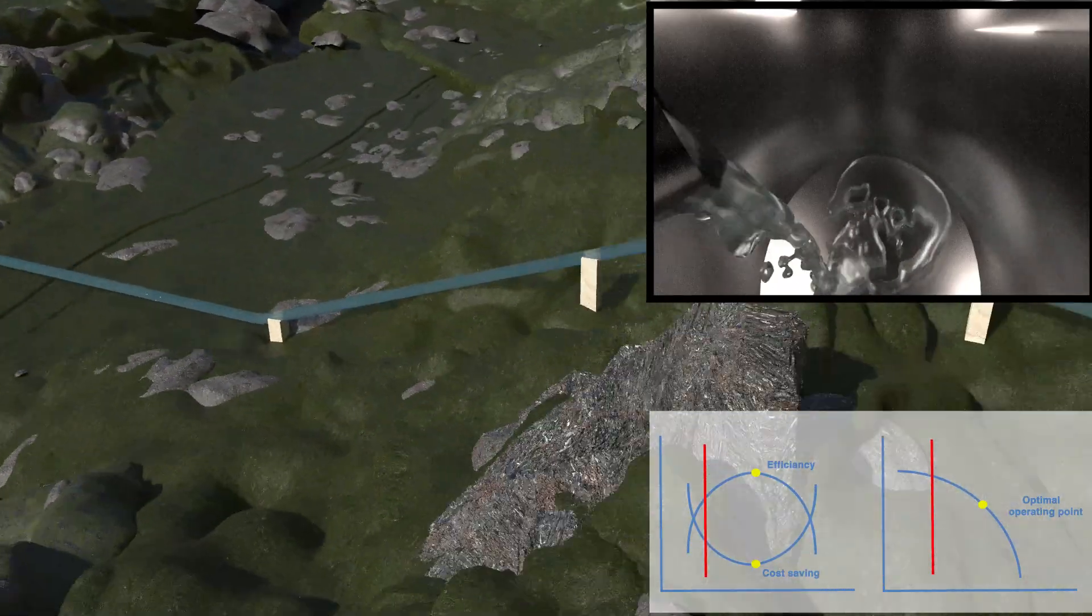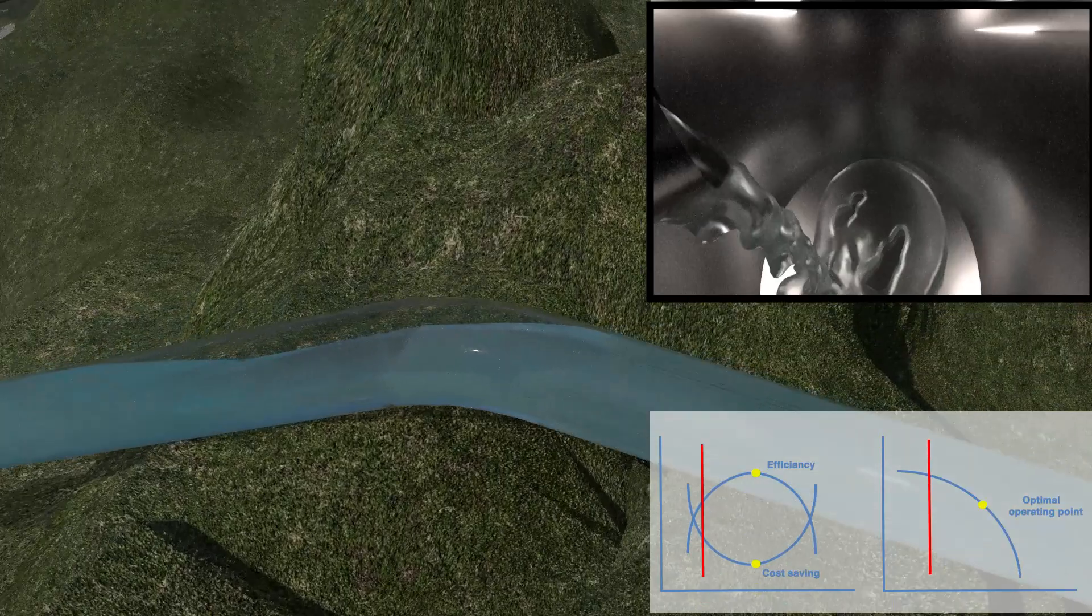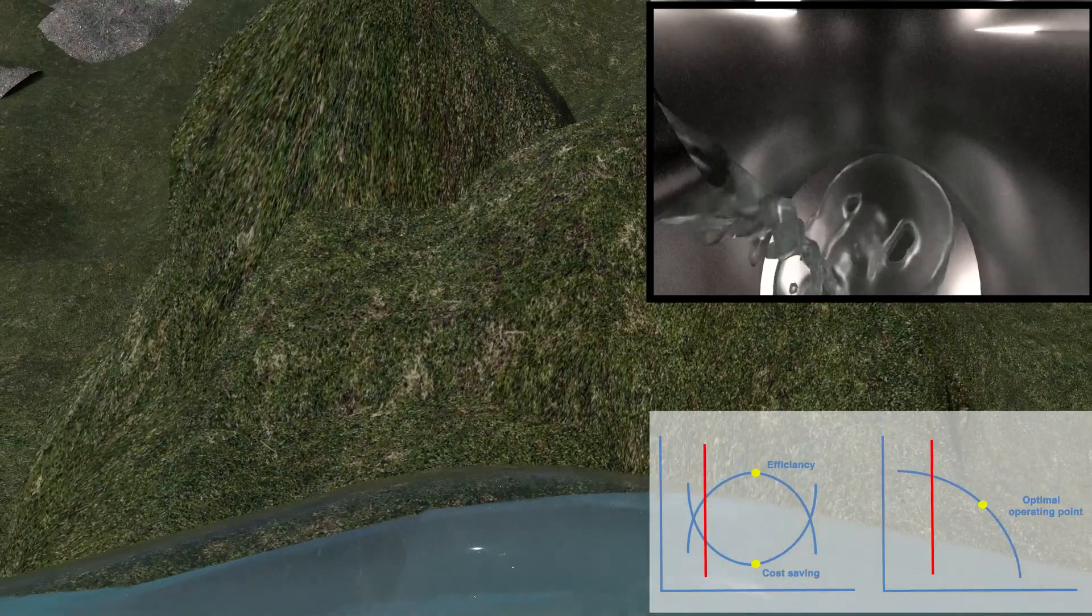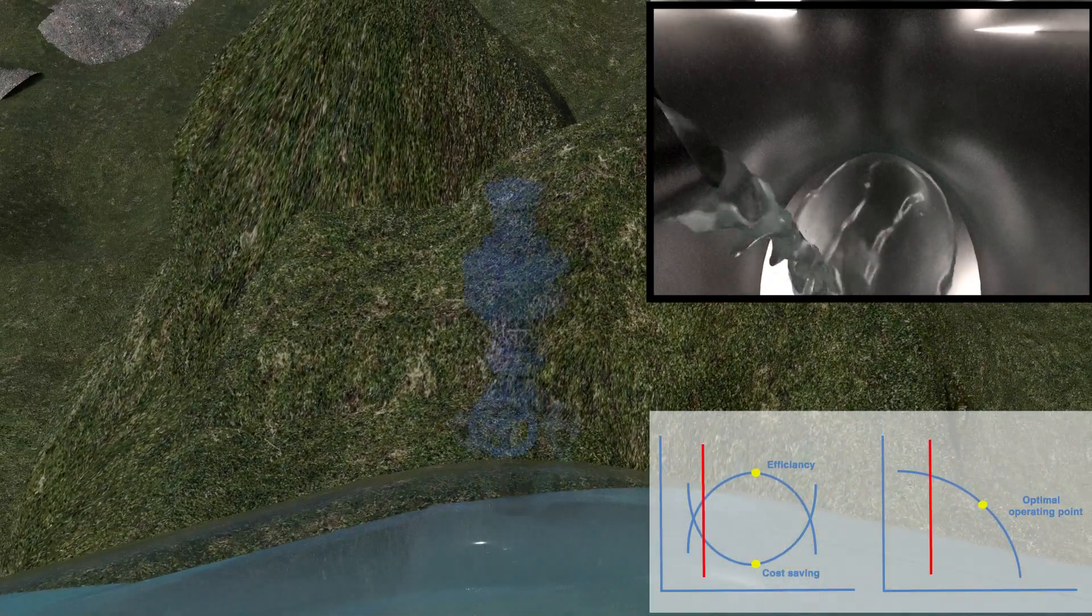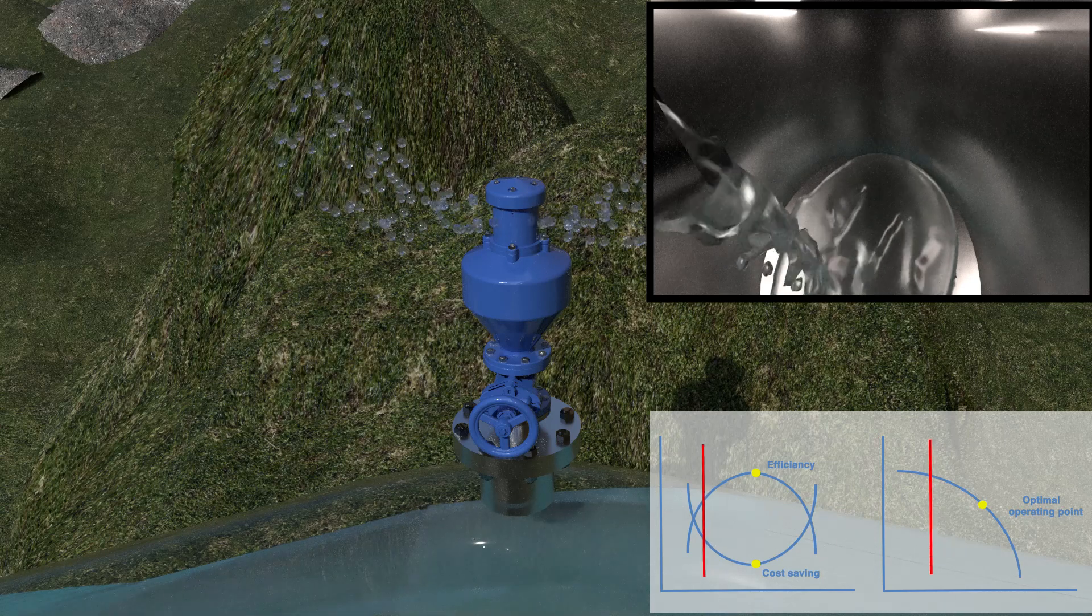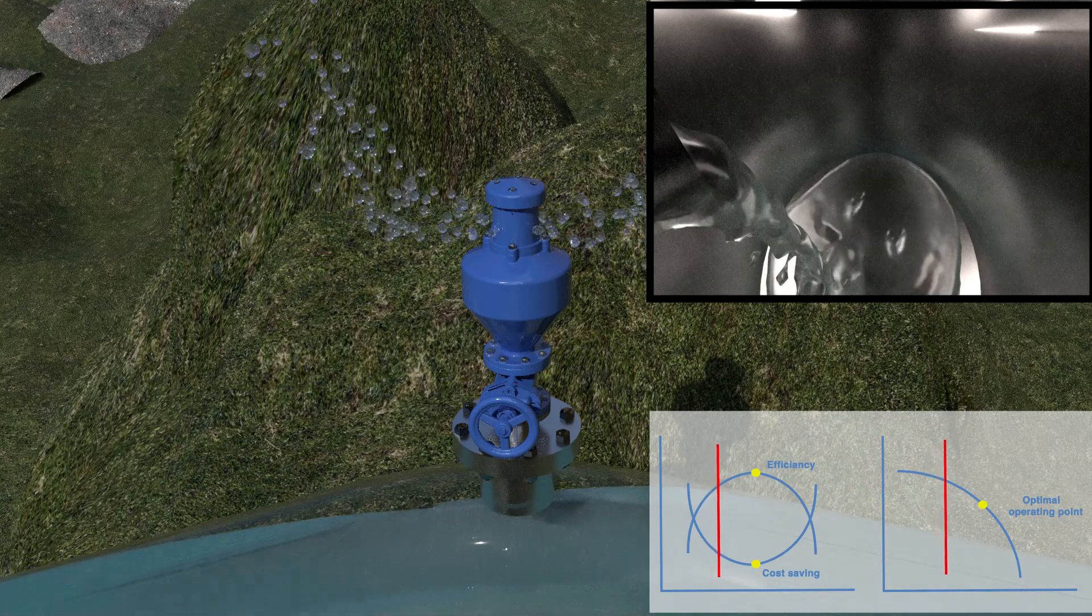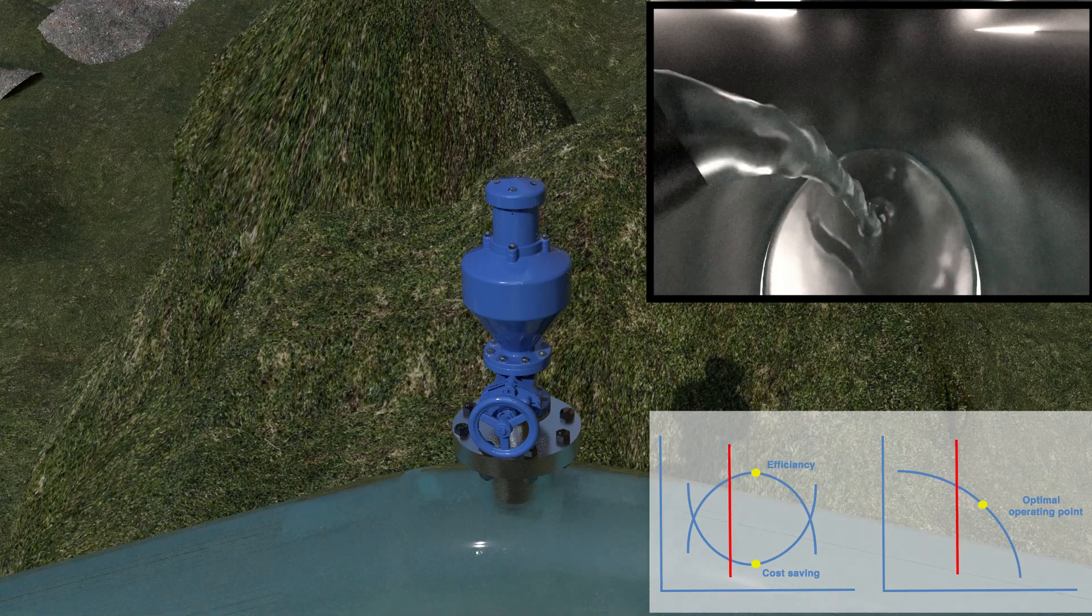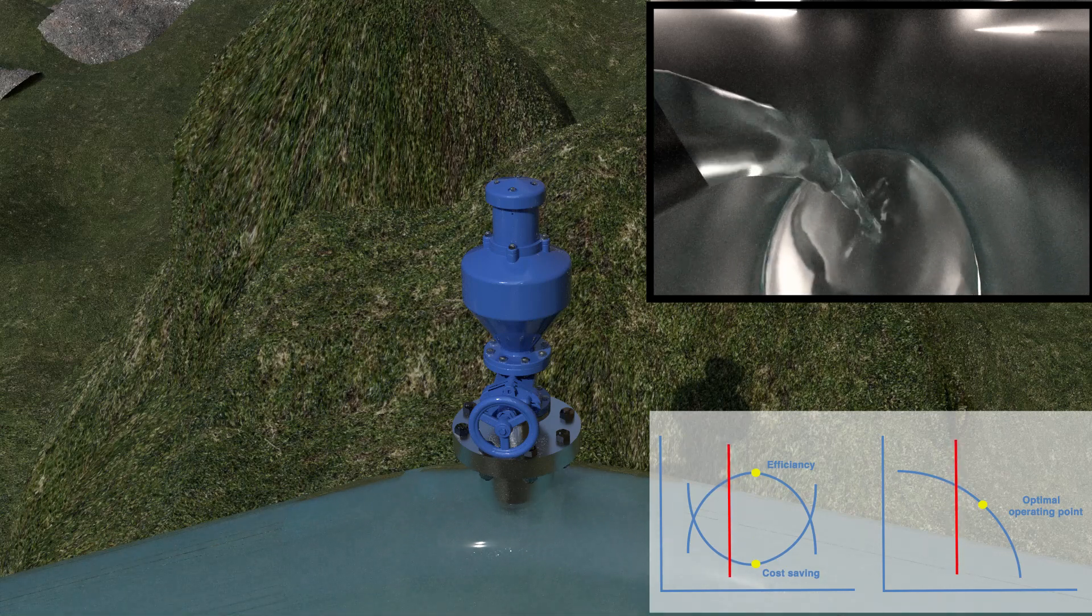The introduction of air valves will ensure the release of air pockets in working conditions, ensuring a higher flow capacity and reduction of cost. This can be clearly observed by the filling of the tank and movement of the red lines.